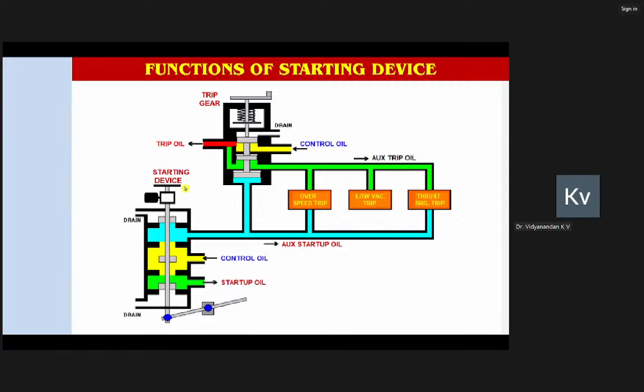So unless you bring the starting device down to the bottom position, that is the 0 position, you cannot reset the master trip device of the turbine, the so-called trip gear. And the trip gear is the source of the most important oil after lubrication, that is the trip oil. Trip oil is necessary for keeping your steam-related valves, such as stop valves, control valves, and NRVs, open. These valves can be kept open only with the trip oil. So whenever any turbine protection operates, maybe overspeed or low vacuum or thrust bearing or lube oil or boiler tripping or generator tripping, the trip oil will drain, and ultimately the draining of the trip oil will close the stop and control valves and NRVs, and that's what we call the turbine trip.